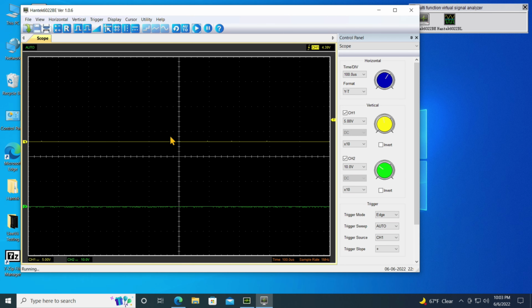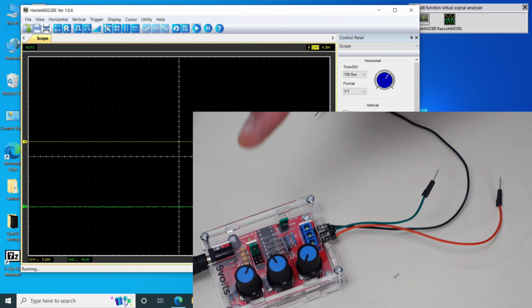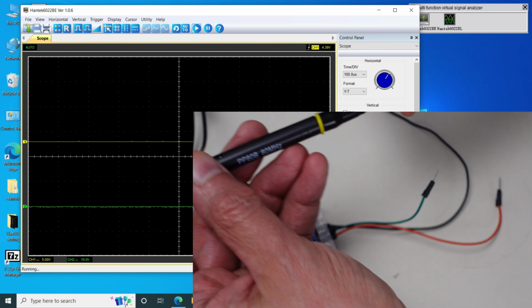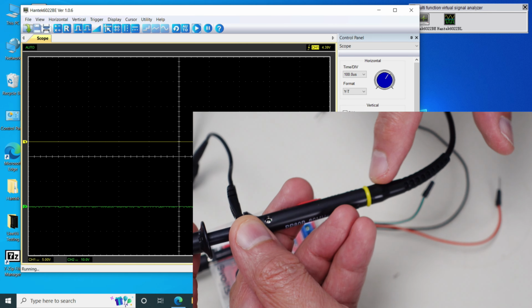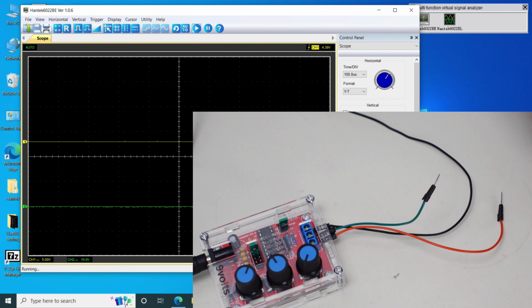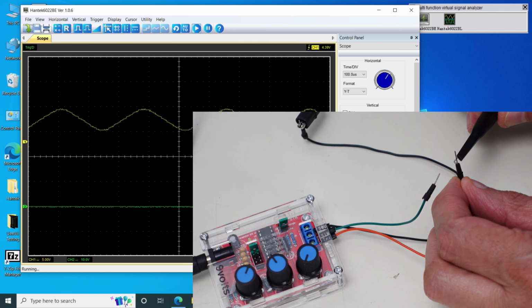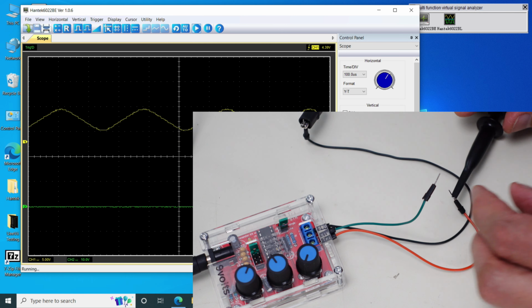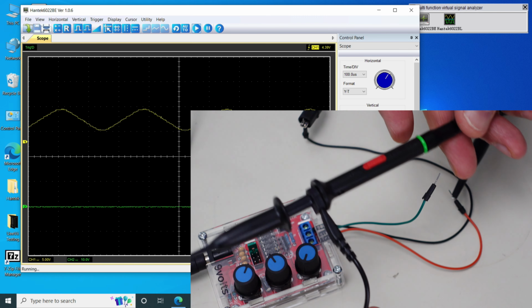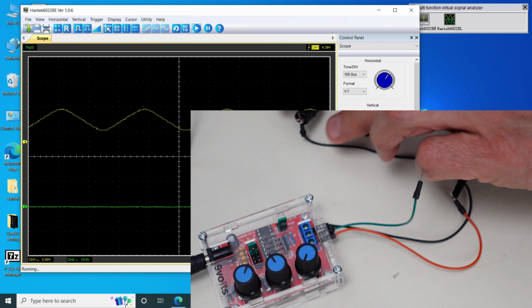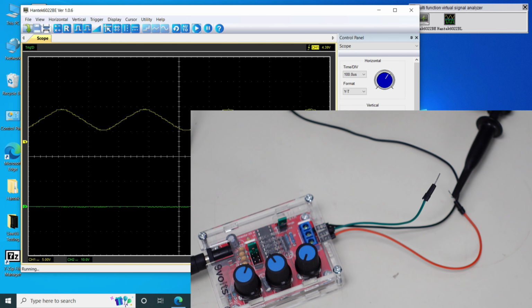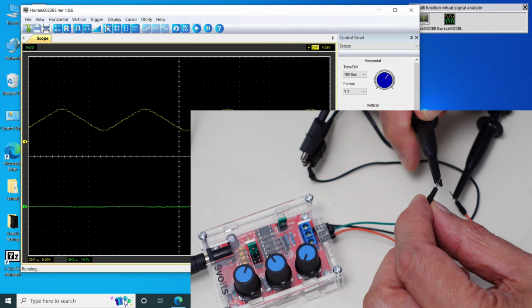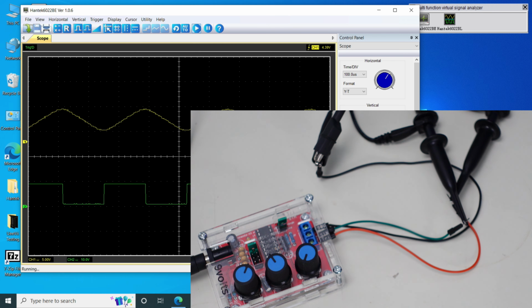And it looks like it's up. I have 2 lines drawn here. Let's connect up one of the lines to my signal generator that I have here. I always like to take the one that has the yellow adapter, which is connected to the first port on the scope. Make sure you connect it up to both the ground and the signal area. So I will pick one. And there we go. I went ahead and picked the one that had the sine wave on it. If I connect the second probe, the one that I currently have with the green connected to it, and I'll connect that one up to the same signal generator, but this is the digital output. Let's see what we get. We get the digital output, so it works.